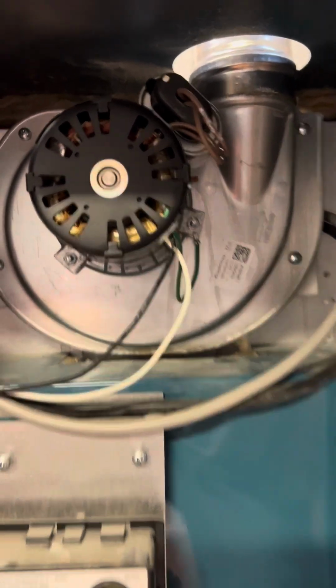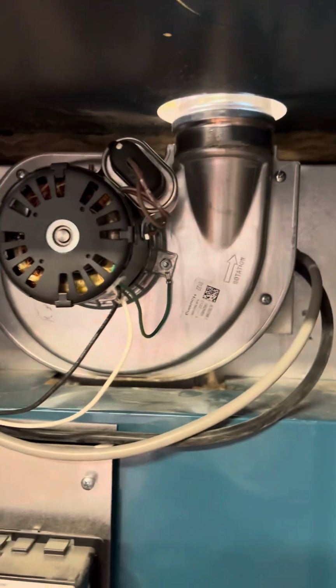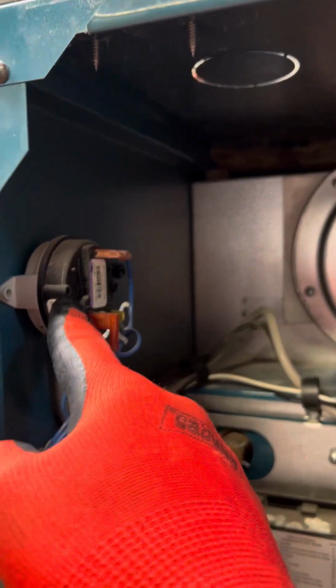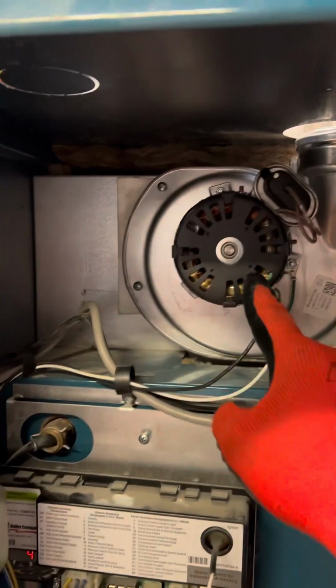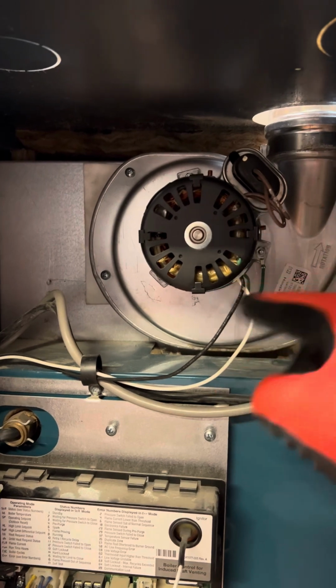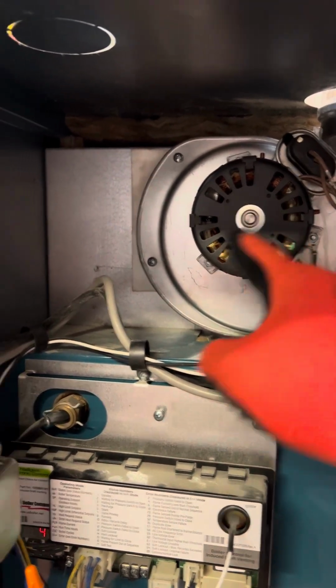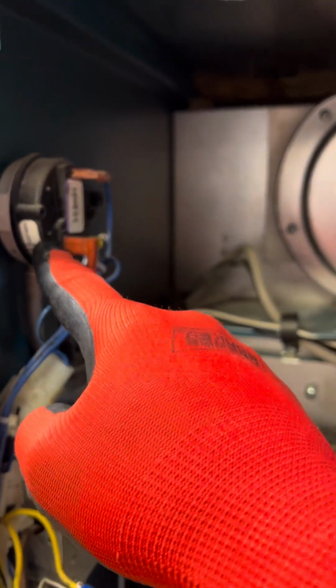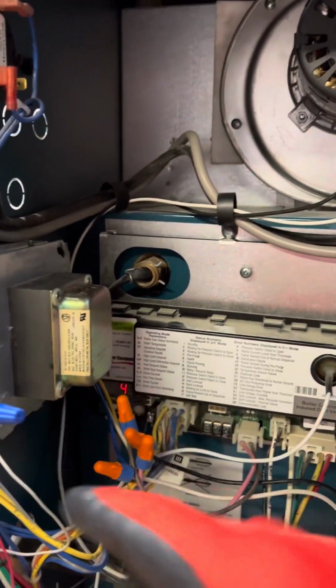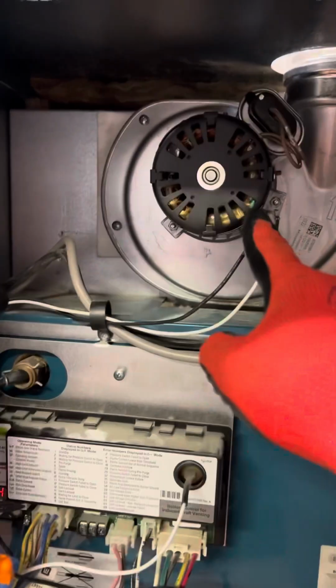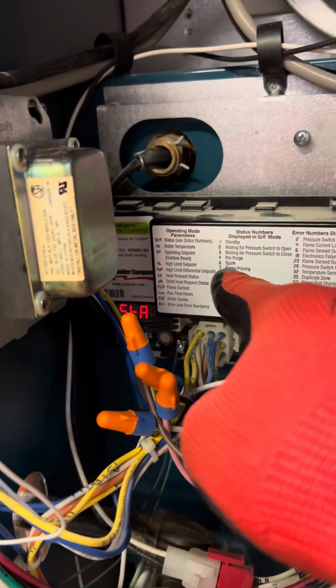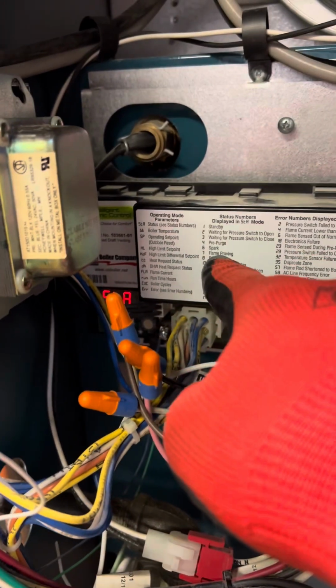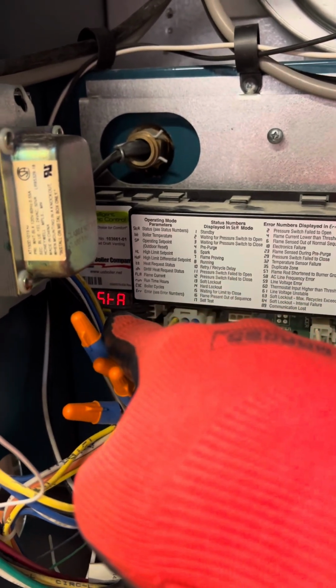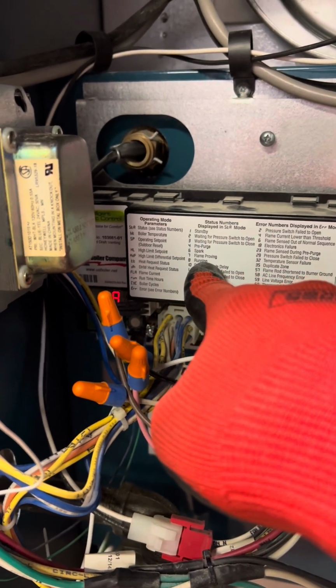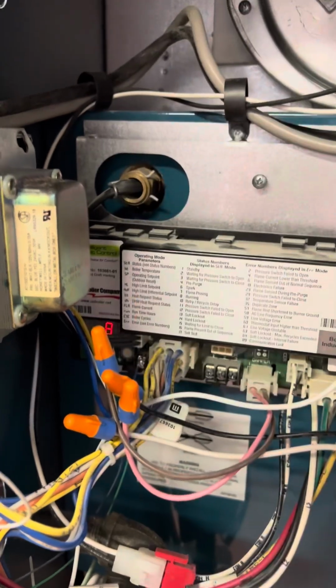After your evacuation pump right here, sucking everything out, this is going to prove that that's on, okay? Because you got to suck out all the gases inside the chamber. So if this doesn't go on, this doesn't close, and then it won't prove it, and then the machine will shut down. So as long as this tube is good and everything, now number 6, that's spark. Number 7 is proving flame. Number 8 is running, guys. So it goes through the whole series.